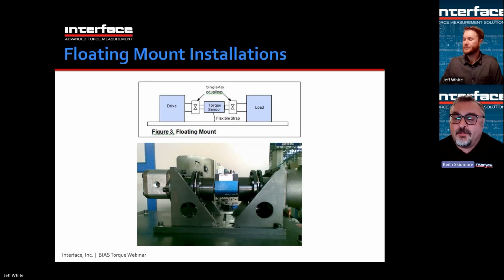And so the couplings allow the torque sensor to sit in the middle, and then the whole system articulates a little bit. So that torque sensor actually moves around a little bit due to the runout in the drive and the load device. And the flexible strap just keeps it from spinning, but it allows it to articulate. Next slide.